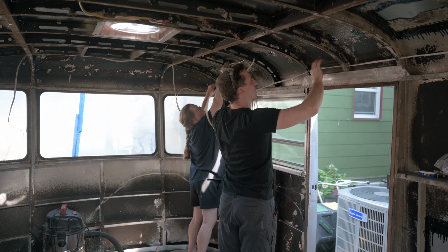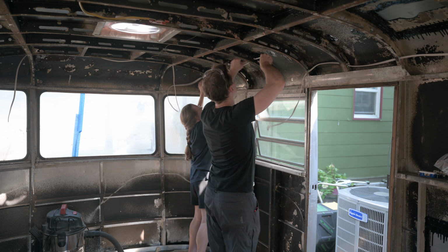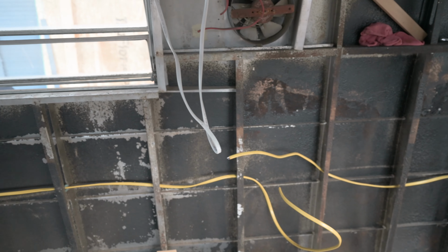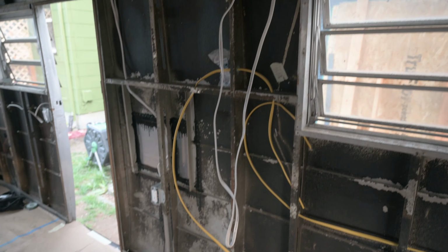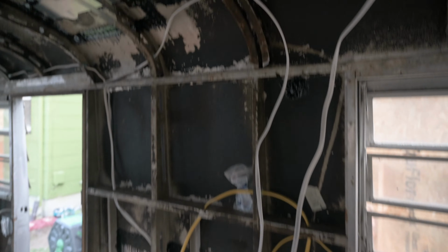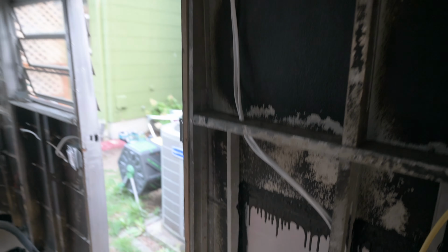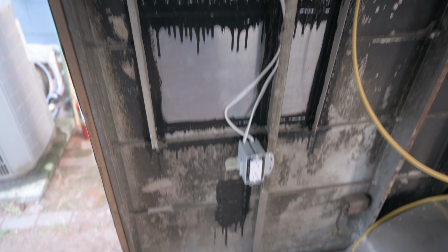If you have a circuit that has many items on it, like we do with our main lighting and non-kitchen outlet circuit, you may find it useful to run it like this. As you can see, we're pulling down loops of the wire to the location of each electrical box and keeping the wire intact and running it all in one go. This allows us to install one electrical box at a time while keeping the rest of the wire intact, so we can test it after each addition of a switch or outlet, just to make sure.